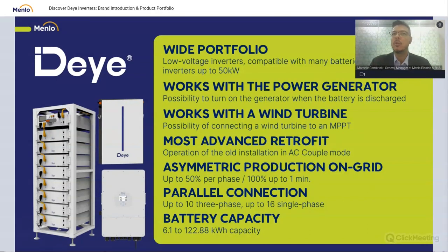It gives you a unique retrofit capability — you can take old on-grid systems and simply add the battery side to the solution. It allows asymmetric production on-grid, up to 50% per phase, and 100% for up to 1 minute. It also allows parallel connections, which we didn't discuss in detail, giving you up to 10 inverters on three-phase and up to 16 on single-phase. And best of all, it gives you a battery range capacity from 6.1 kilowatt hours up to 122.88 kilowatt hours.